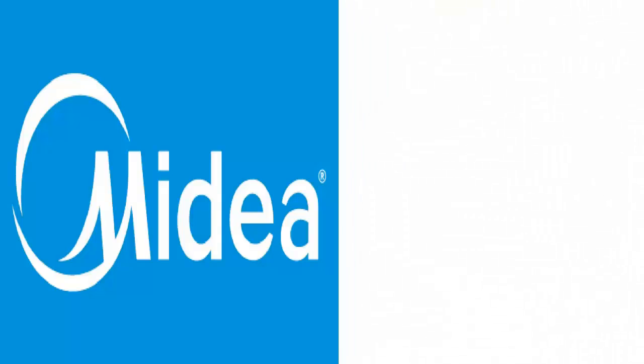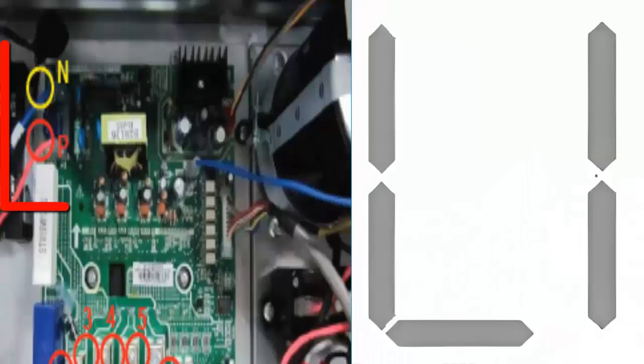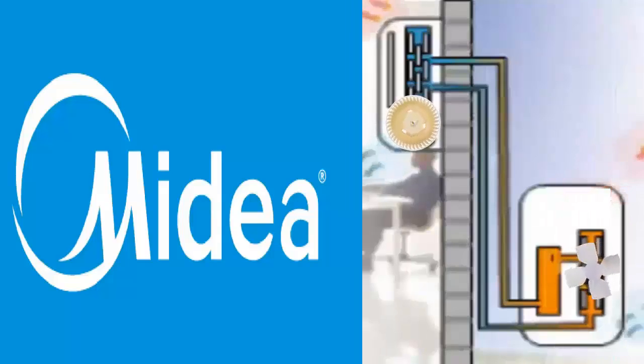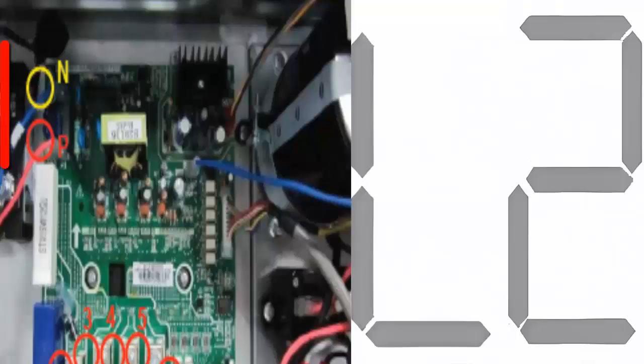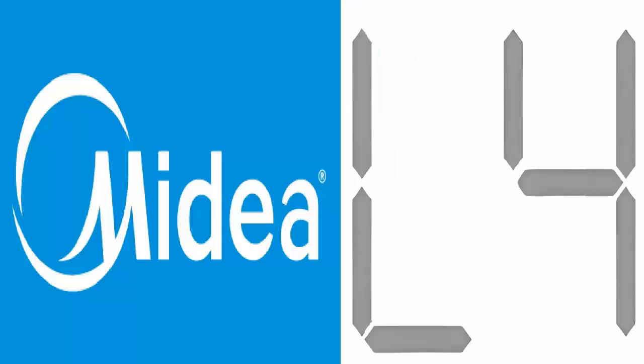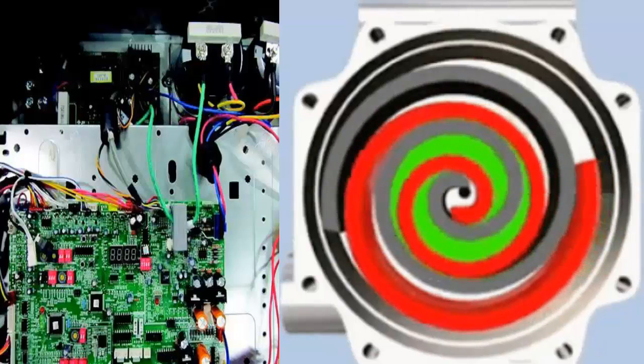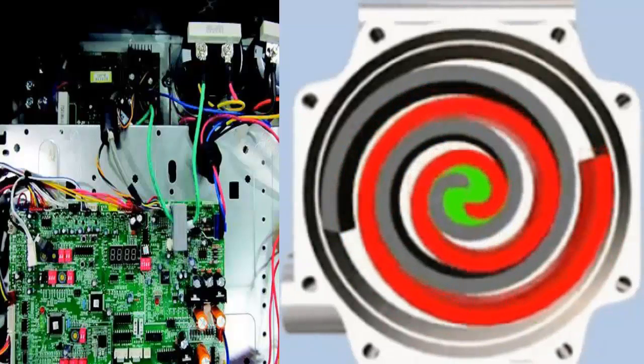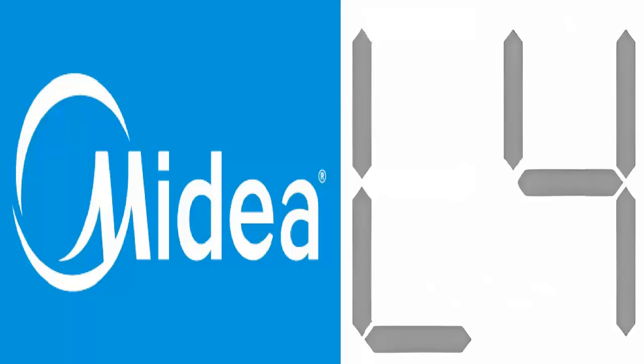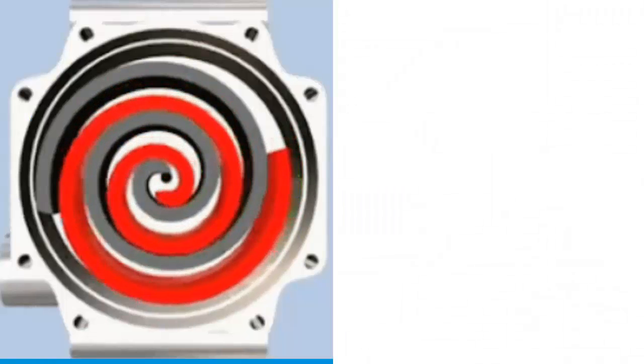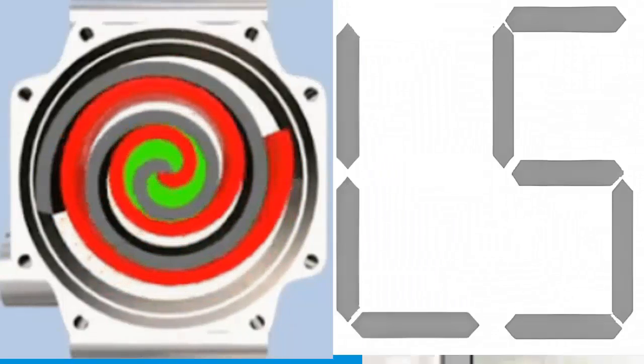The code L1 signifies protection due to the presence of low voltage. The code L2 signifies protection due to the presence of high voltage. The code L4 indicates a compressor motor control error called an MC error. The code L5 indicates that the compressor is not reaching the appropriate speed.